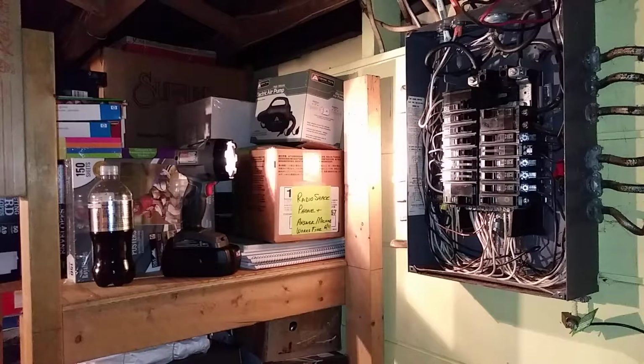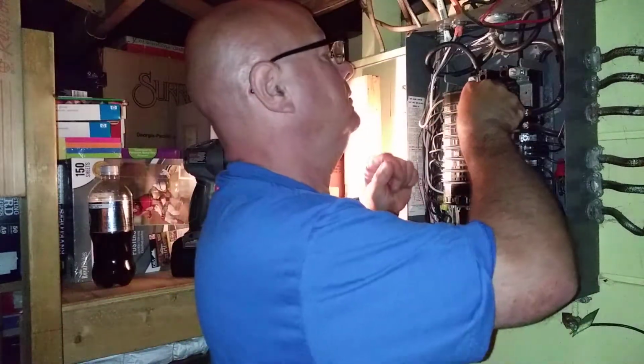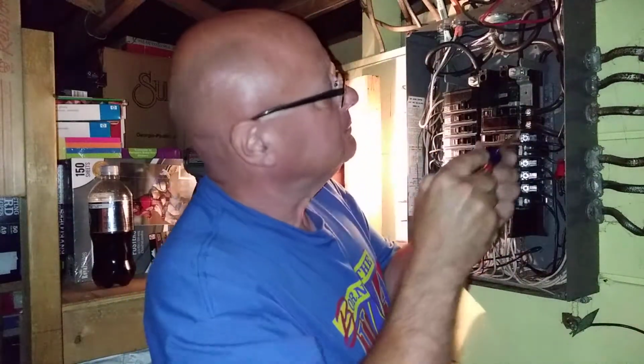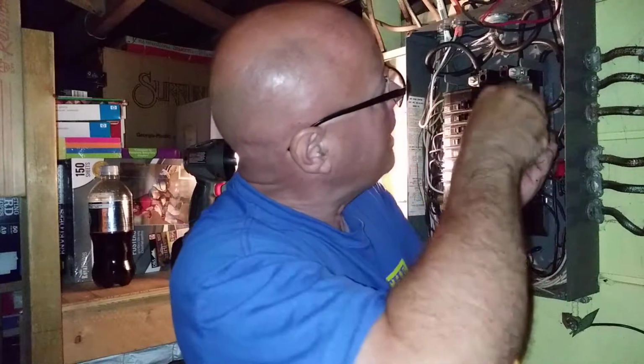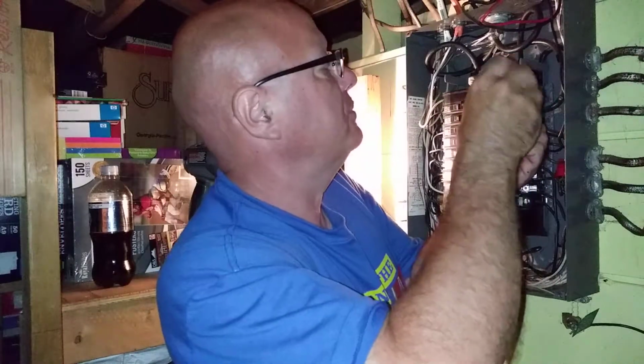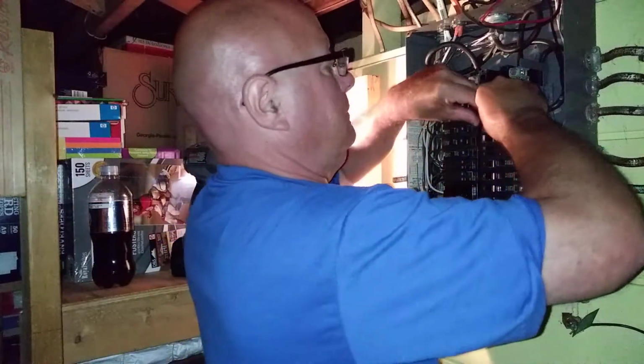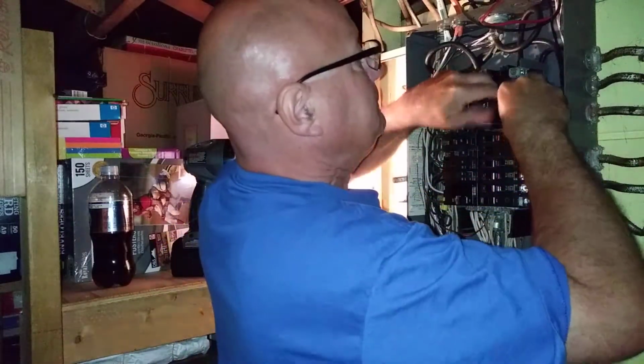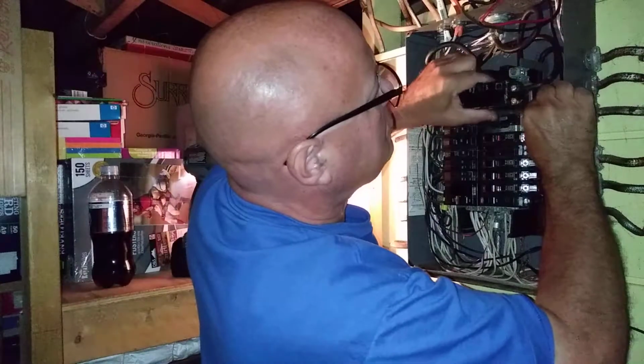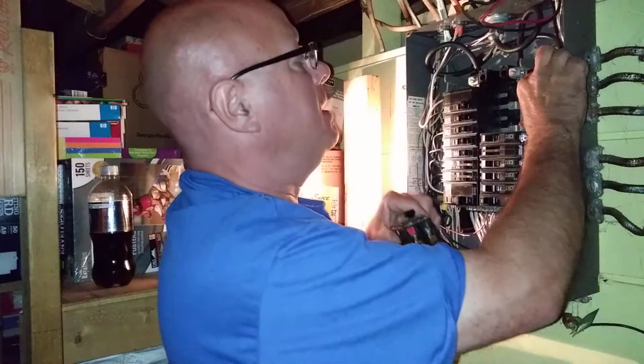All right, the two last ones we have are... Okay, so now we're going to replace this big 60 here. Hey, that connection wasn't even tight. On the wire, you mean? Yep. Hey, that one wasn't even tight either. Can you imagine all these years? That wasn't even tight. Son of a gun. That's the critical one, too, of all. Yeah. Obviously, it worked, but not that.